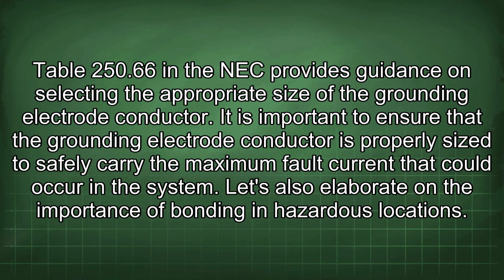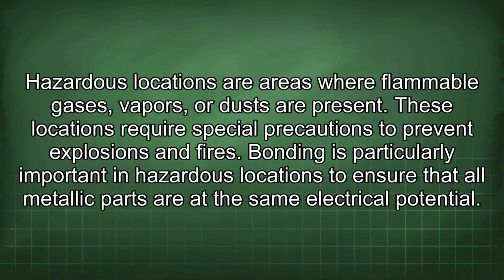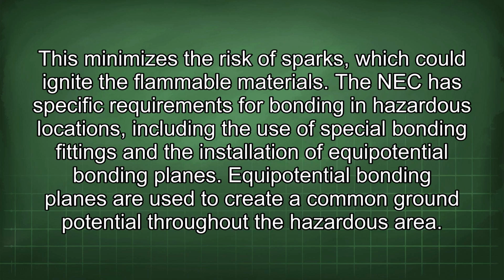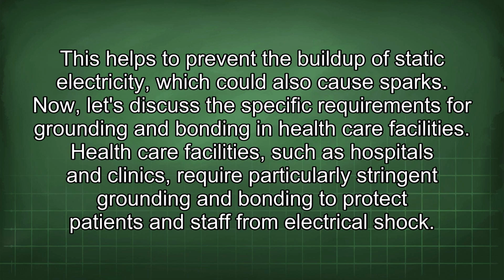Let's also elaborate on the importance of bonding in hazardous locations. Hazardous locations are areas where flammable gases, vapors, or dusts are present. These locations require special precautions to prevent explosions and fires. Bonding is particularly important in hazardous locations to ensure that all metallic parts are at the same electrical potential. This minimizes the risk of sparks, which could ignite the flammable materials. The NEC has specific requirements for bonding in hazardous locations, including the use of special bonding fittings and the installation of equipotential bonding planes. Equipotential bonding planes are used to create a common ground potential throughout the hazardous area. This helps to prevent the buildup of static electricity, which could also cause sparks.